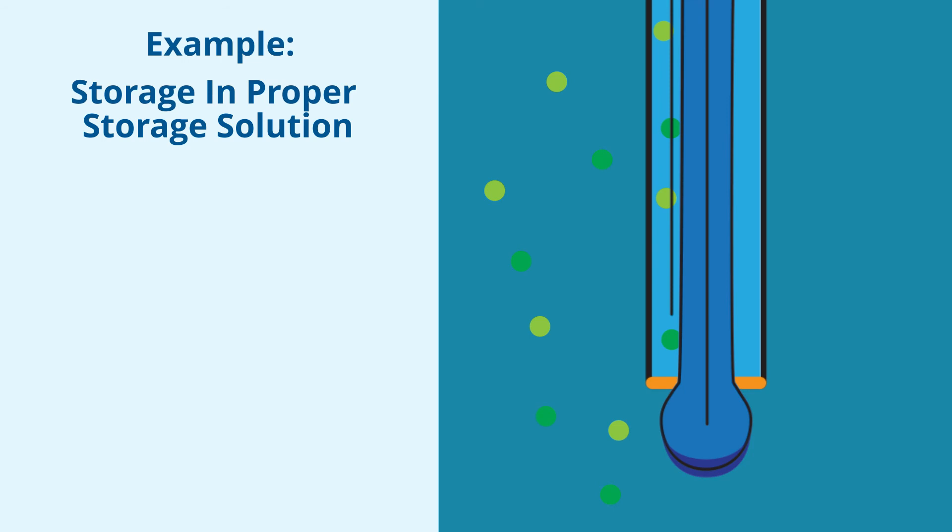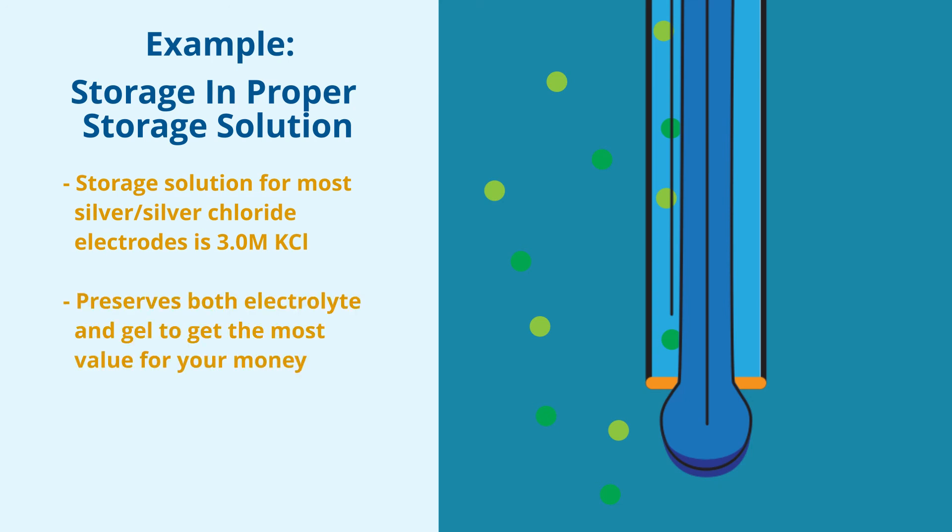Lastly is storage in proper storage solution, which for most electrodes is 3 molar potassium chloride. Fully saturated KCL solution is also fine. Unlike water, 3 molar KCL does not reduce the lifespan and allows you to get the full value out of your electrode, something which I think we're all trying to do considering how expensive they can be.